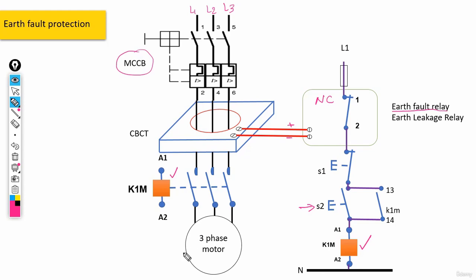Okay, now guys, once more, for any kind of reason, it doesn't matter what, if we ever got any fault current, we would get this signal here, more precisely, a positive signal here. And this positive signal causes the normally closed contact to be opened. And then the electrical current would be cut off, the contactor would stop working, and as a result of everything, the motor would be turned off. And yeah, guys, basically this would be another method that we can use for applying further earth fault protection in our three-phase motors. Now, let me give you an example.